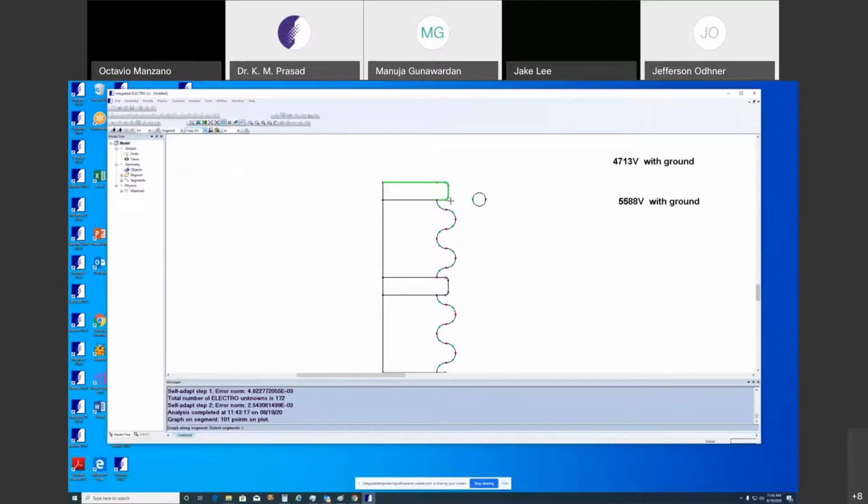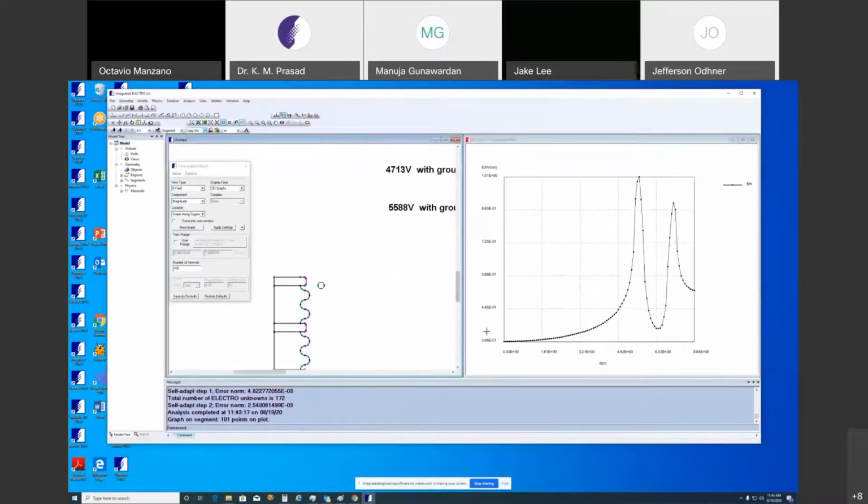The electric field will be on side of A. Okay. Can you see that? So somewhere here, obvious, understand that because there's a segment which has got a rounding there. The field is maximum at that place. That field is 10 kV per centimeter. That is the field there.